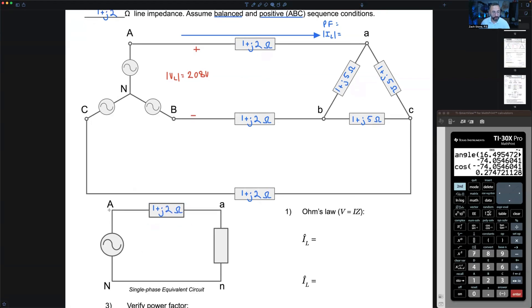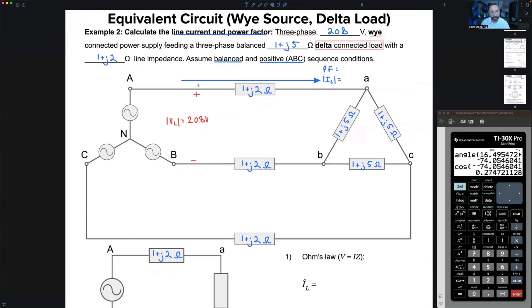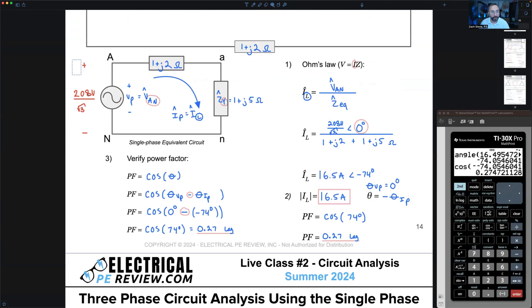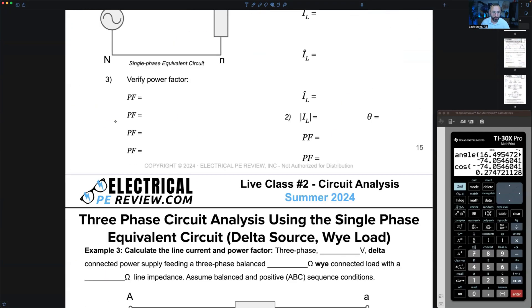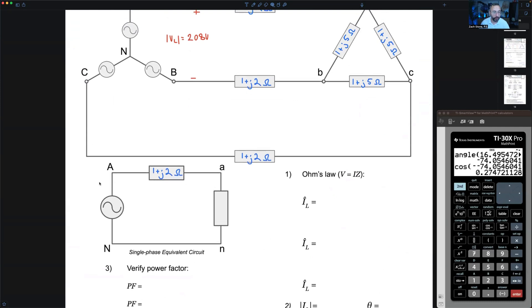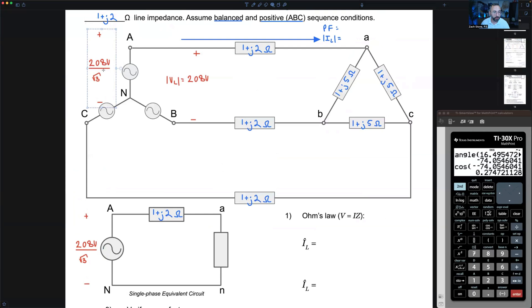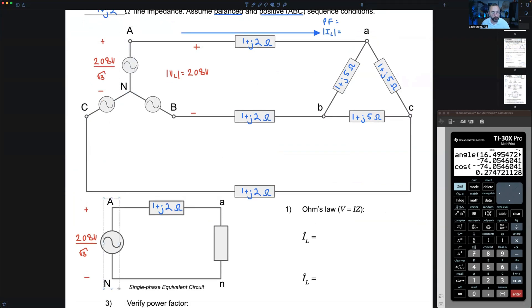What about our voltage A to neutral? If I've got 208 volts from A to B and it's Y connected, then from A to neutral I take my line voltage 208 volts and divide it by the square root of three. That's our Y phase voltage from A to neutral in our single-phase equivalent circuit.